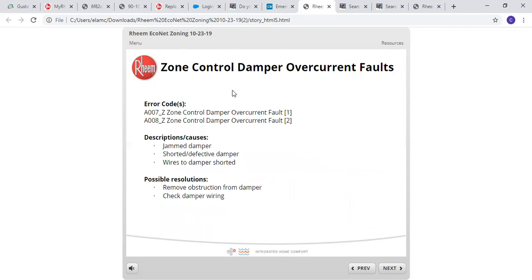Zone control damper overcurrent faults. You'll get these faults on the Econet. In this case here, you have an A007Z, zone control damper overcurrent, fault 1, A008Z, zone control damper overcurrent, fault 2. Some descriptions and causes: you could have a jammed damper, shorted or defective damper, or you could have wires to the damper that were shorted. And so if you get something in there obstructing it, you will get this fault. So possible resolutions: remove any obstructions from the damper, and then double check your damper wiring.